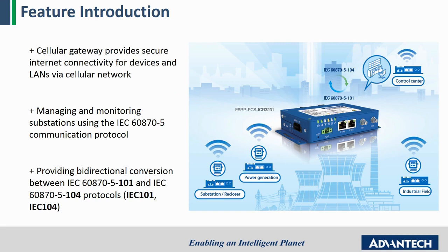Energy SCADA applications are more or less standardized with the IEC 60870-5 communication protocol. The IEC 101 version is defined for serial line communication and is used in legacy devices using serial ports that are still widely deployed.